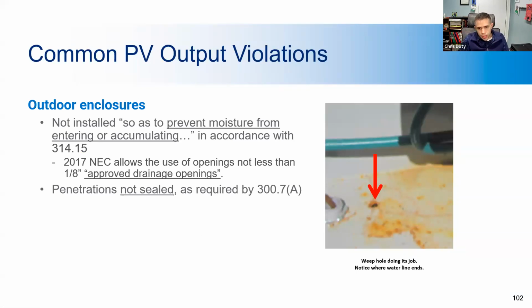Here we have an example of a common issue with an enclosure itself. Code allows for the use of what's called weep holes, which effectively allow water to exit an enclosure to avoid pooling. Weep holes are used to prevent moisture from accumulating in an enclosure. You don't want it to be pooling in an electrical enclosure for obvious reasons. So here you can see that the water line ends where the weep hole is, so that shows that this was effectively draining the water. And obviously you want to make sure that these are not sealed, as they're specifically for allowing water to leave the box.